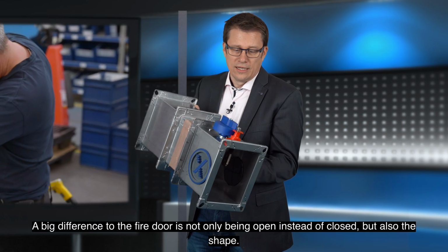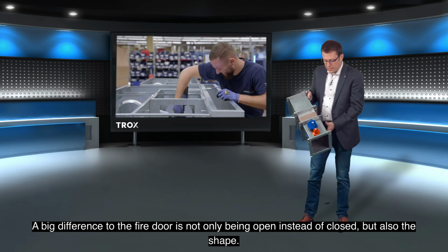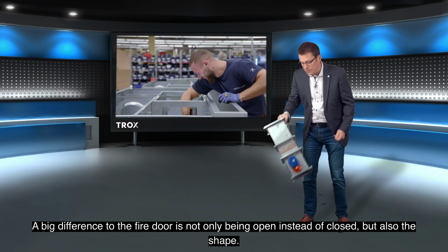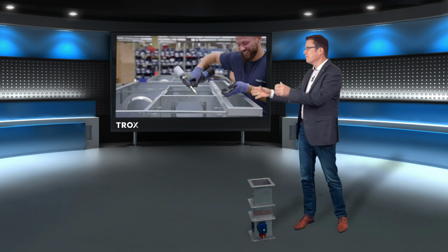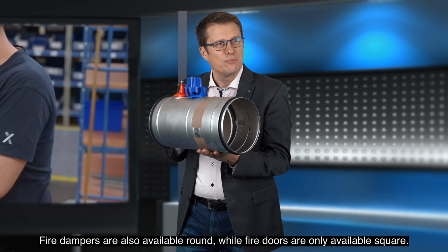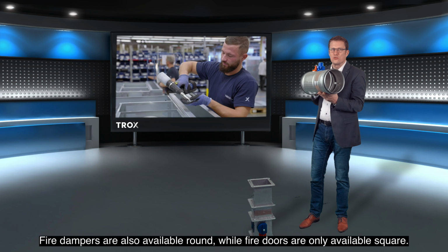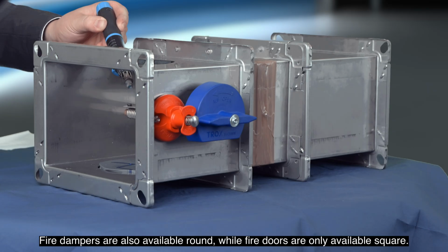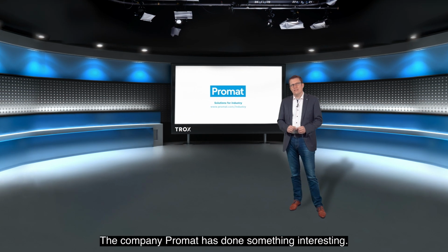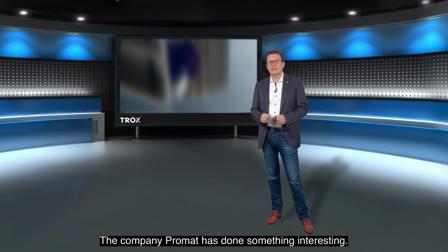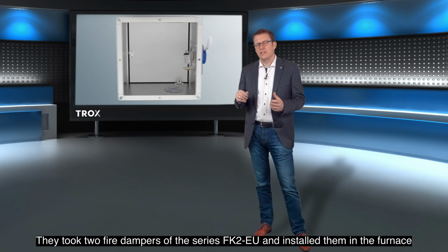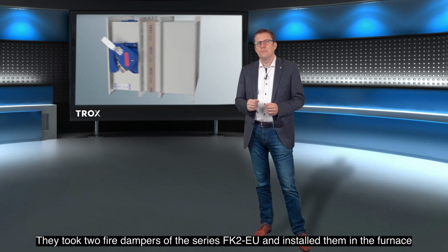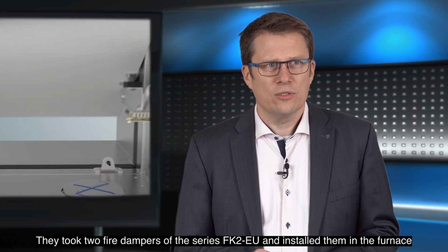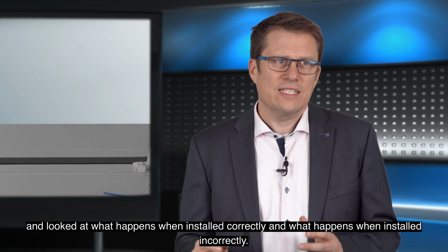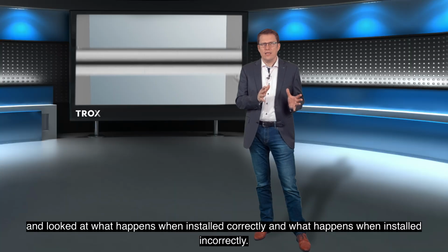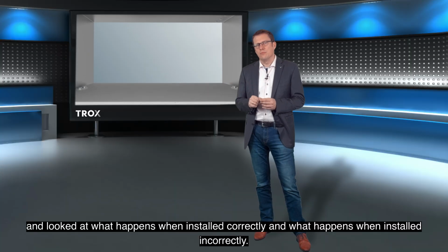A big difference to the fire door is not only being open instead of closed, but also the shape. Fire dampers are also available round, while fire doors are only available square. The company Promat has done something interesting. They took two fire dampers of the series FK2EU and installed them in the furnace and looked at what happens when installed correctly and what happens when installed incorrectly.